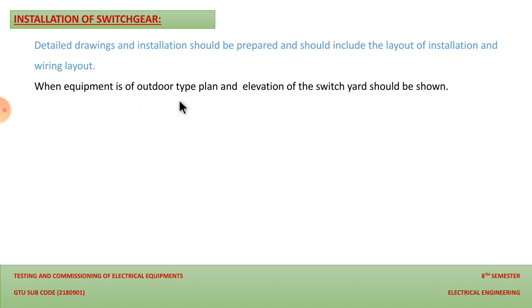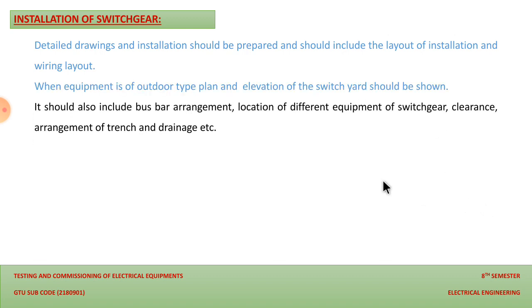When the equipment is of outdoor type, that is, when we want to use our machine for an outdoor purpose, the outdoor plan and elevation of the switch yard should be shown. According to the plan, we have to install our device so that we can protect our instrument from unwanted surges and other factors like a contaminated atmosphere, and so that we can do maintenance in future without any hassle. The next point for the installation of switchgear is that it should also include the bus bar arrangement, location of the different equipment of switchgear, clearance, and arrangement of trench and drainage, etc.